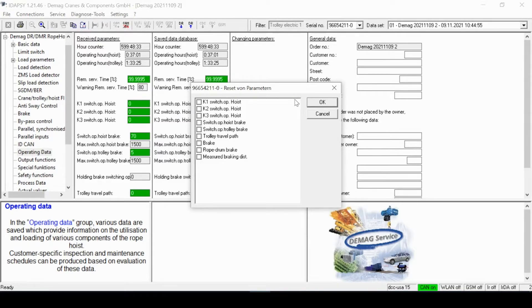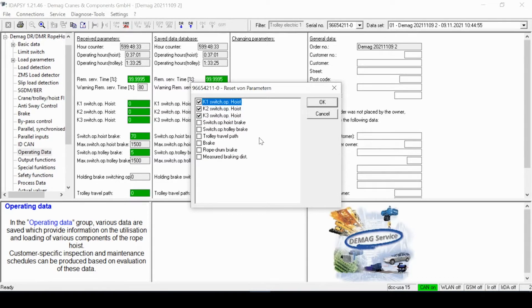This opens up a box in the center of the screen which shows me the equipment that physically could be changed on the crane or adjustments that could be made — it's simply a checklist. If I put in a new control board, I get a new K1 contactor and I'll put a check mark in that block. I also get a new K2 and K3 contactor for speed and direction, as well as a new relay for the trolley brake control. And now I say okay.